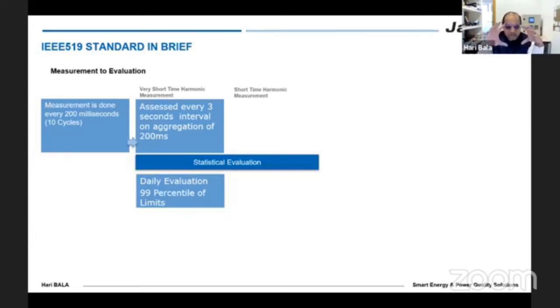So it is pretty complex to do over an Excel sheet, because as I said, you will be doing it for 28,800 samples for TDD and individual harmonics 1 to 50, which means for individual phases that is 150 parameters, and then the TDD is 3 parameters. So you will have 153 parameters of data managed for 3 seconds in a daily value, and then you will have to do the calculations, which is pretty tough. And that is where the meter manufacturers come in handy to help you out in this case.